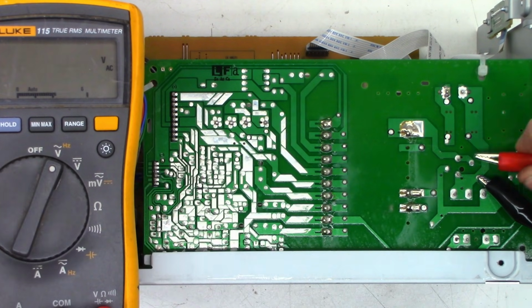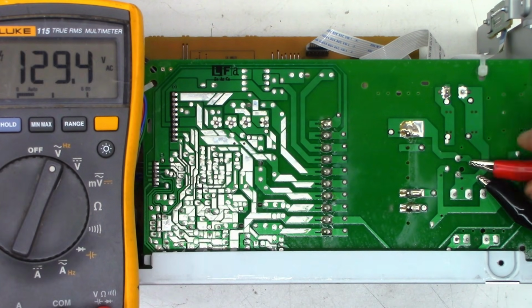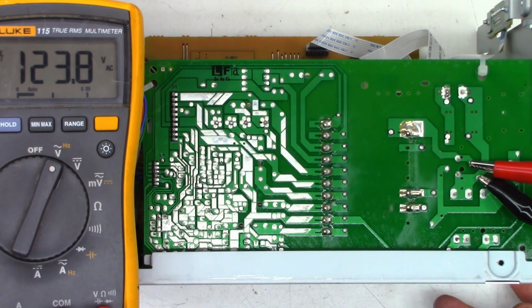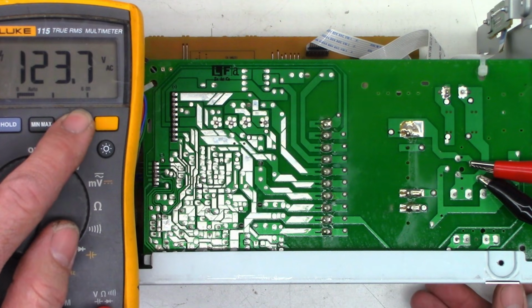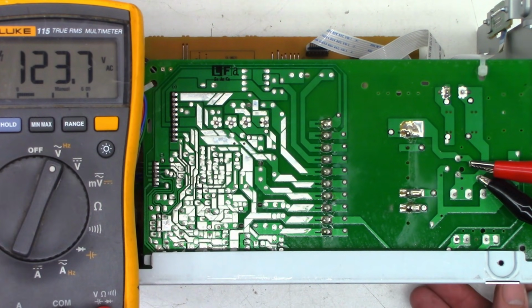So we're in AC, we should see 120 volts there, and we do. Got the voltage up a little bit high. I'll put this in manual, so when I press the power button this should go to 0. And it stays at 123 volts, so the relay is not actually engaging. I do hear a click though. I wonder if the relay is just stuck.